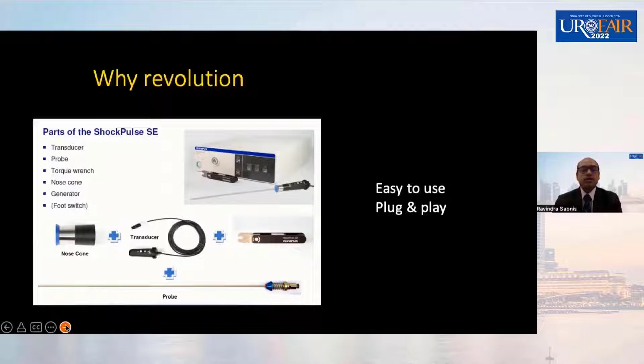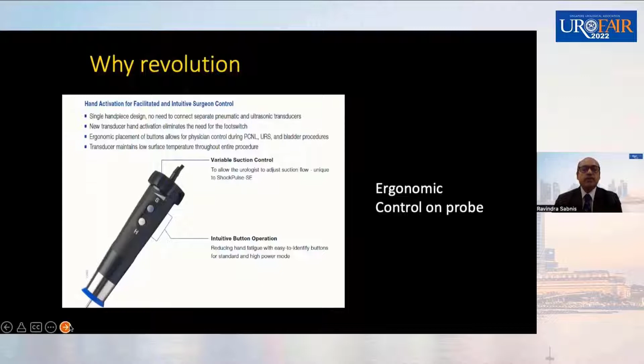Another important revolution is that everything is hand controlled. The surgeon himself can decide whether you want a high setting or a standard setting. This is for suction. You can reduce or increase the suction. Everything is in your hand. And over and above that, the transducer design is very ergonomic, very lightweight, so there is no fatigue to the surgeon.